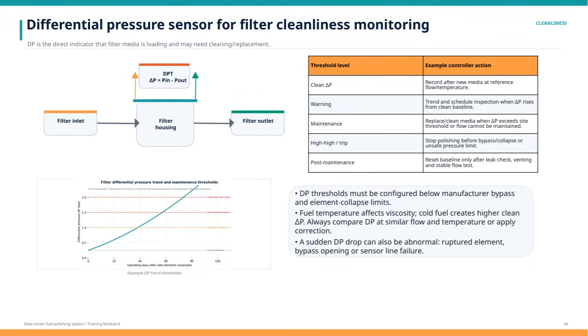Here, we're focusing on the differential pressure sensor and its role in monitoring filter cleanliness. Differential pressure, or DP, is a key measurement indicating how much the filter media is loading up with contaminants and whether it might need cleaning or replacement. Essentially, DP is calculated as the difference between the pressure at the filter inlet and the pressure at the filter outlet, which directly tells us how clogged the filter has become. We track this pressure difference against several threshold levels. When the filter is clean, we record a baseline delta P at a known flow and temperature. As the filter starts to load, we enter the warning stage, where the trend of rising DP signals that inspection and scheduling maintenance is needed.